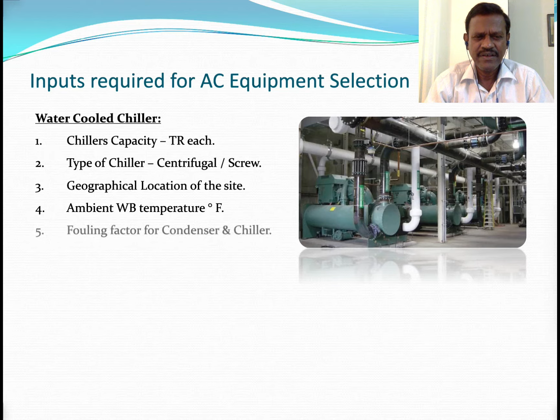In some cases you will have a centralized cooling tower and get condenser water from there. In that scenario you have to specify the temperature you are going to give and the outlet leaving temperature you require; both temperatures you have to specify. If it is an independent dedicated cooling tower for the chiller, then you need not specify these; based on the wet bulb temperature, you specify the cooling tower outlet temperature you will get.